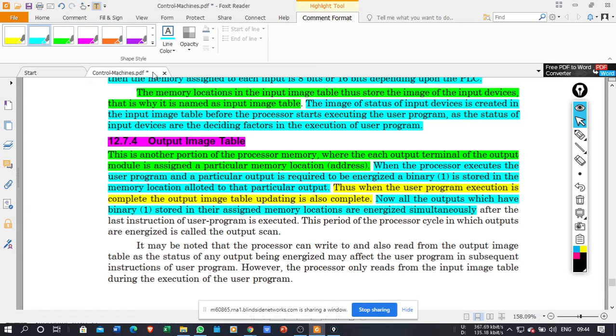Here the word simultaneously is very important. All the outputs are energized at the same time, after the last instruction of the program is executed. This period of the processor cycle in which outputs are energized is called the output scan cycle.